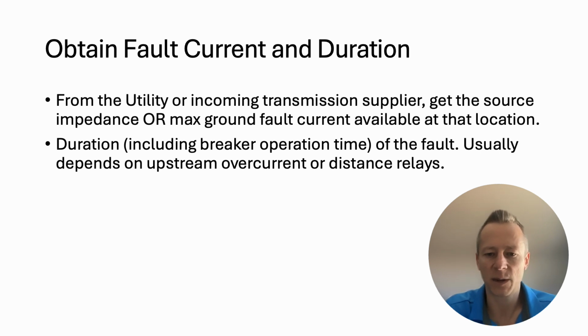If you have just high-speed distance protection, maybe you're much faster and you're much closer to just a few cycles for the distance protection to actuate and get to the relay, and then 3 to 5 cycles for the breaker to operate itself.